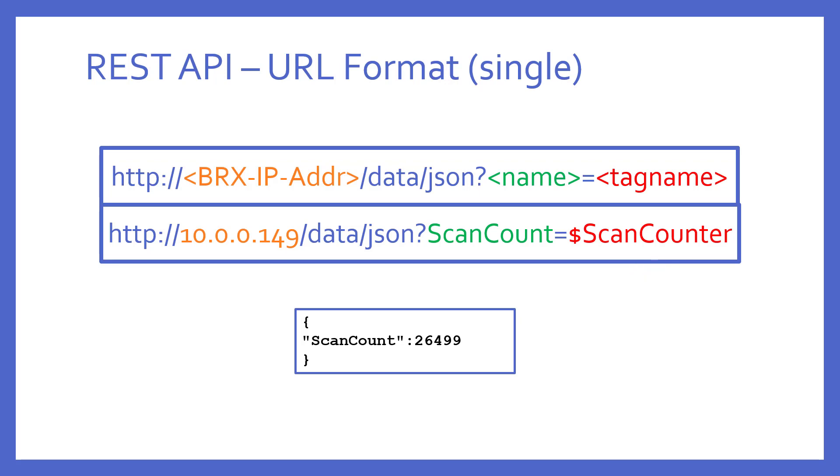This would change the example here to use dollar sign scancounter, which is the tag name of the system element DST0. The result, of course, would be exactly the same. You need to keep this very important thing in mind because most people, when programming a PLC, utilize tag names extensively simply because it makes more sense to have a familiar name for the elements used rather than the raw, less relevant element name itself.